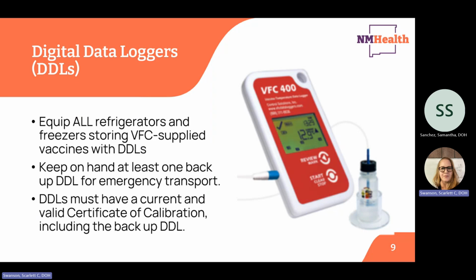Equip all refrigerators and freezers, your primary, your backup, any overflow, or any other temporary unit storing VFC supplied vaccines, with VFC compliant digital data loggers. For purpose-built auto-dispensing doorless units, built-in internal data loggers must meet VFC program requirements, except for buffered probes, which are not required. The New Mexico VFC program requires the use of the VFC 400 data loggers unless a written request for an exception has been submitted and approved in advance.